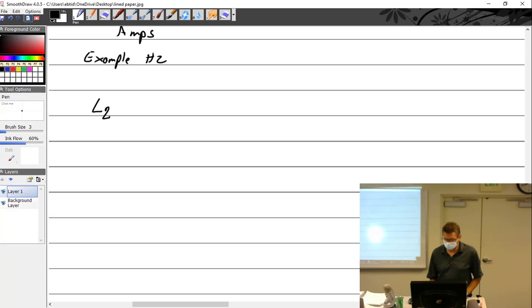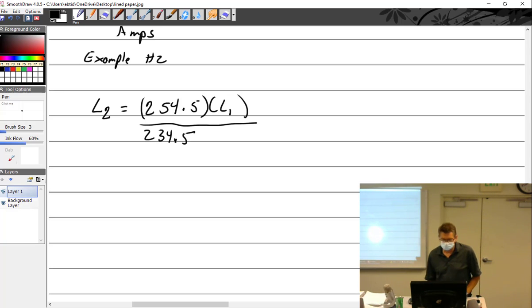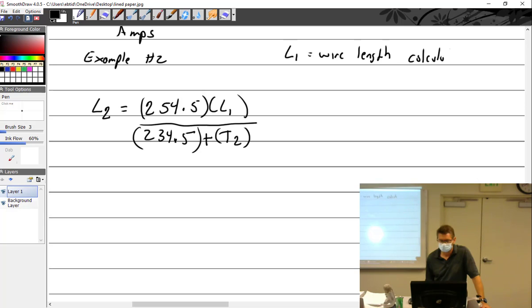So it is L2 equals 254.5 times L1, divided by 234.5 plus T2, where L1 is the wire length calculated, L2 equals the new wire length, and T2 is the wire temperature.